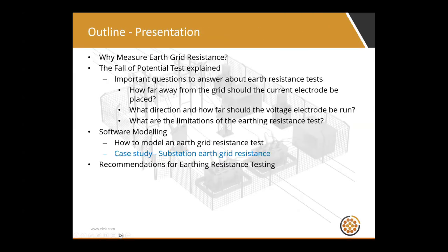The outline of the presentation will be as follows. Why do we measure earth grid resistance? How do we do that? We will explain the fall of potential test, and we'll answer some important questions about that test, including how far away should the current electrode be placed, what direction and how far should the voltage electrode be run, and what are the limitations of that test. We will talk about software modeling, how to model an earth grid resistance test using software. We will provide 2 case studies actually, and we'll examine the results of those. And finally, just to assist you in your roles in power systems, we'll provide some recommendations for earth resistance testing that you can take away with you.